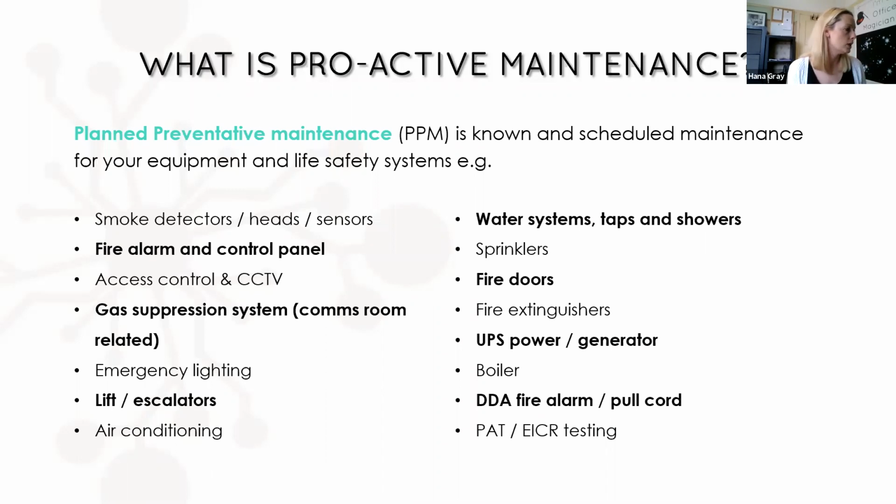It's a fire safety mechanism that starves the oxygen in the room, hopefully suppressing any fire that's in there. So if you have got something like that, or any early particle detection systems, sometimes manufactured by companies like Vesda, make sure that they're also being checked and maintained. Emergency lighting, obviously that will need to be checked monthly and annually.